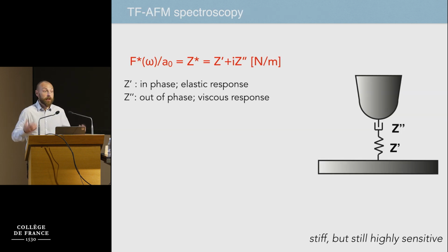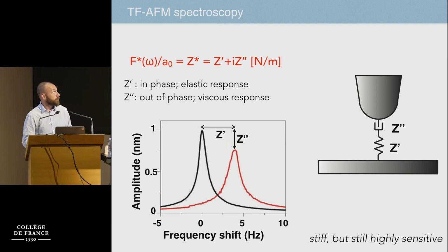And what you measure is basically the mechanical response of the tuning fork. You do not measure directly the mechanical response of the liquid, but you measure how the oscillator responds. In our case, it's a resonance measurement, so we investigate what is happening at its resonance, and we can separate the two components. One is the conservative force, that is basically the shift in the resonance frequency, and also the dissipation or the damping force that is translated by this change in the oscillation amplitude or increase of the width of the resonance.